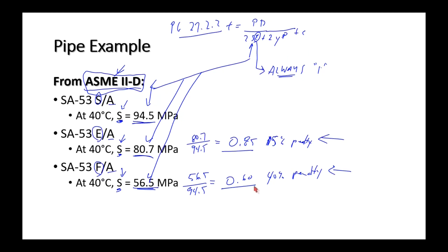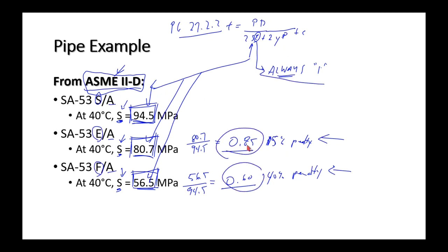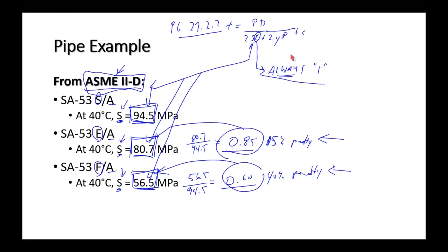ASME 2D builds the joint efficiency penalty into the stress values themselves. Notes in ASME 2D say: forget about using an efficiency factor for your pipe — just use the S value and always use E = 1, and they've taken care of the 0.85 and 0.6 penalties by adjusting the listed stress values for each material. Therefore, for piping calculations, E is always equal to 1.